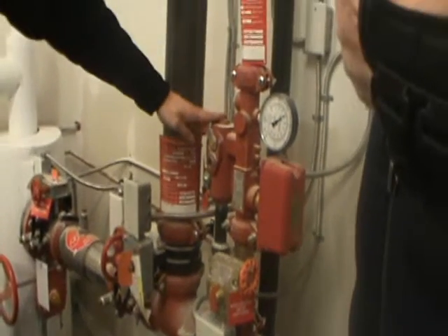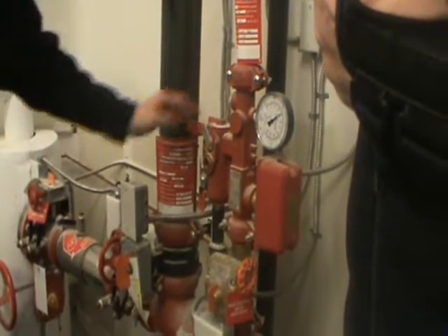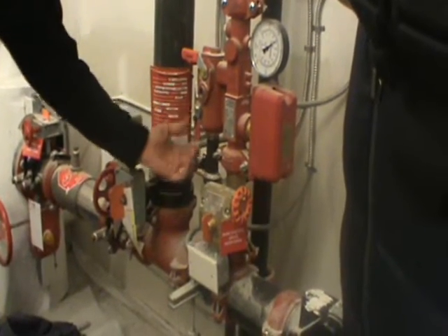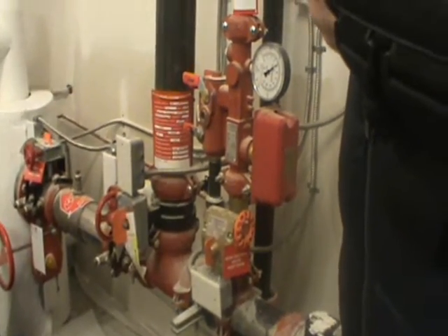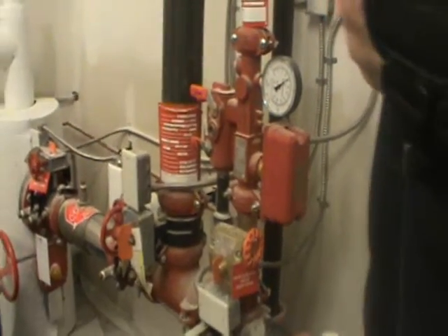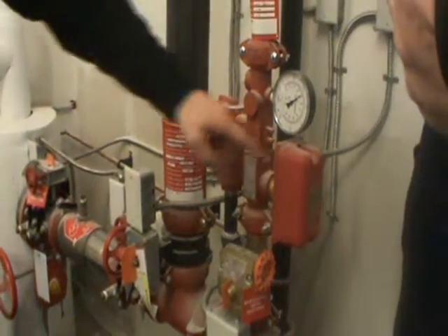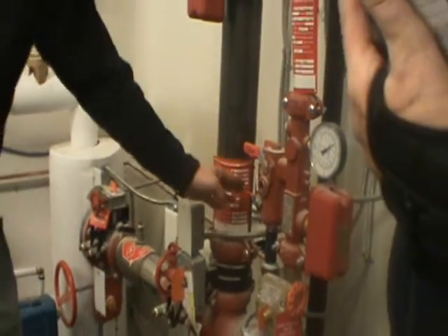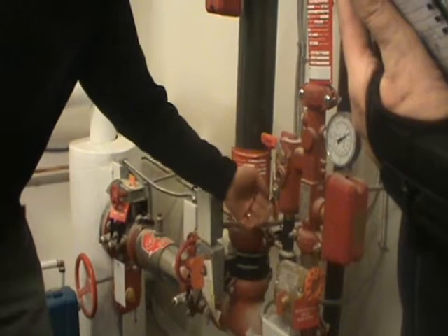You also have what they call a test and drain assembly. You have a valve that's closed and a drain position. For annual testing, you just flip the valve to the test position and open the valve — that will trip your flow switch. Once you get the annunciation at the fire alarm panel, simply shut the valve again, let the system drain down, and put it back to the drain position.